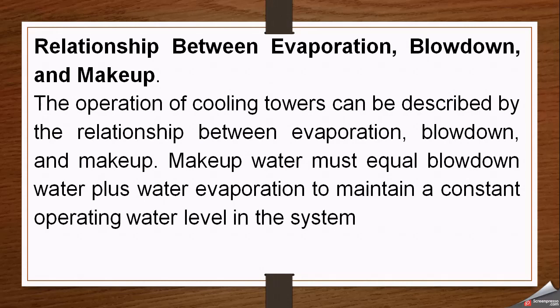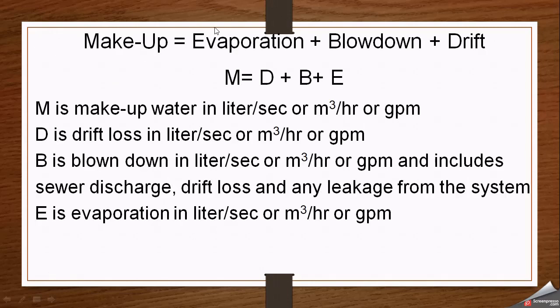There is a relationship between evaporation, blowdown, and makeup, because makeup water normally covers the losses from evaporation, drift losses, and blowdown. The expression used to calculate the amount of makeup water required is: makeup water = evaporation + blowdown + drift. This must equal makeup water to maintain a constant operating water level in the system.